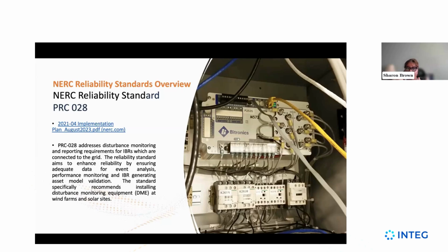I think what came out of this particular standard was that this equipment is expensive, and depending on the size of the site, you're going to have to install fault monitoring equipment if you don't already have it. So you have disturbance monitoring equipment at these different locations—fault recording, sequence of events reporting. The whole purpose of the data collection is so you can glean details about disturbances, collect data on IBR performance during a grid disturbance, and also validate your ride-through capabilities. You want to use this disturbance monitoring data to identify and address any performance issues.